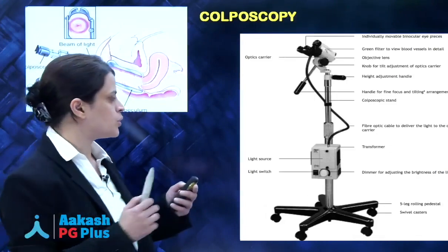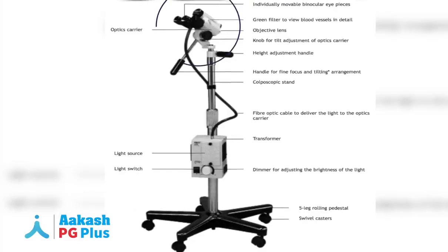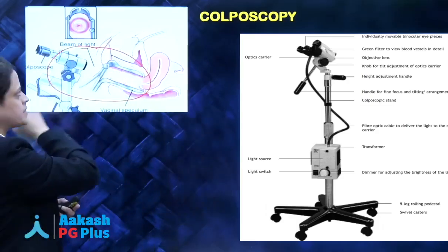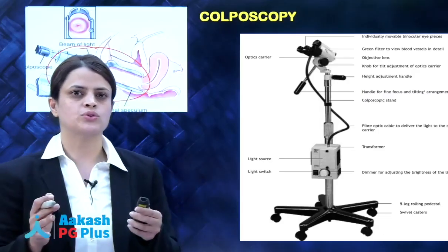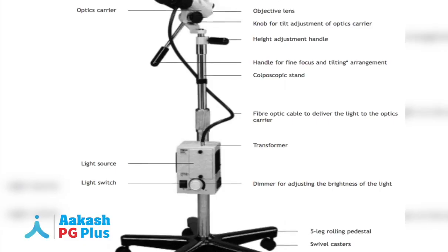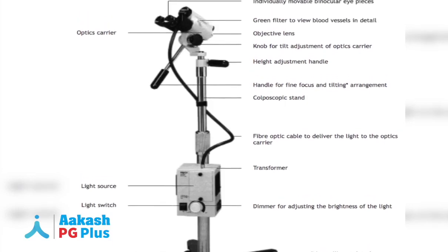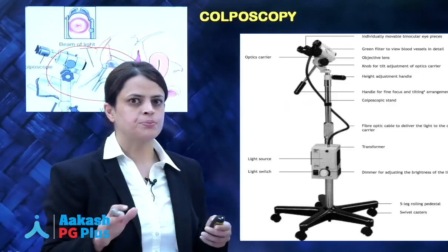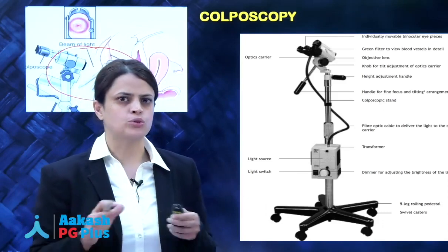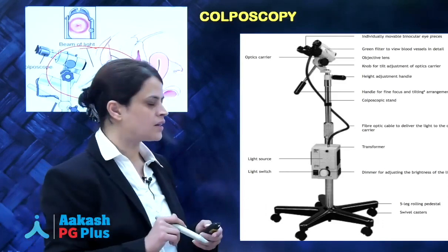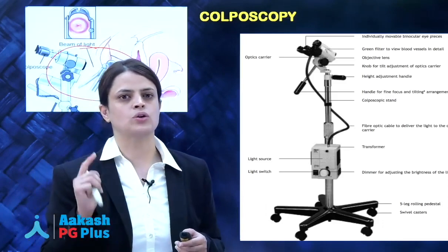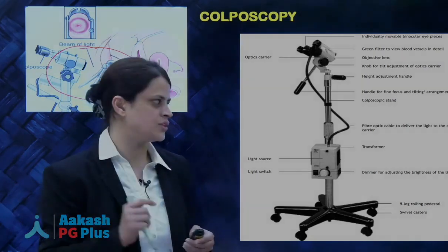A colposcope is essentially a low-power binocular microscope which helps us to visualize the cervix under magnification. Normally the colposcope produces 16 to 40 times magnification of the cervix. Colposcopy is usually done as an outpatient procedure — most hospitals have a colposcope installed in one of the OPD rooms. There are three steps to a colposcopic cervical procedure.